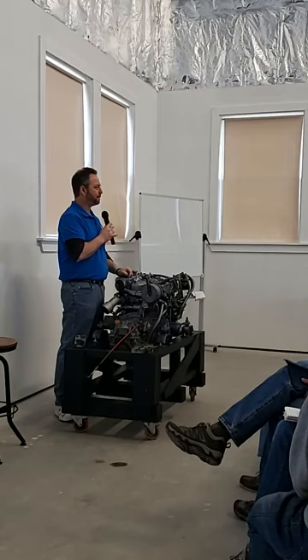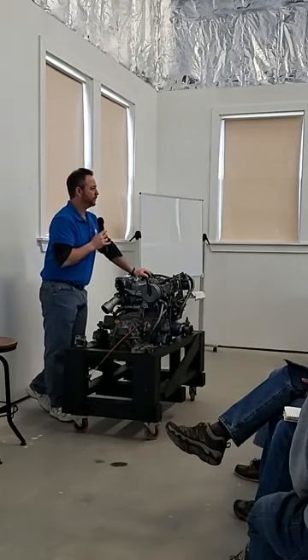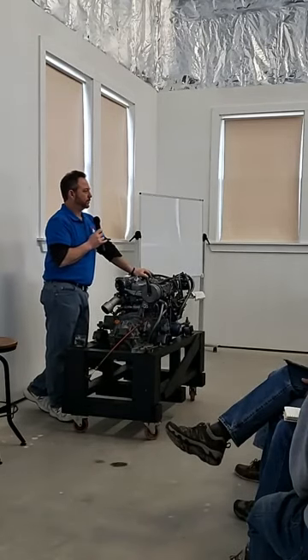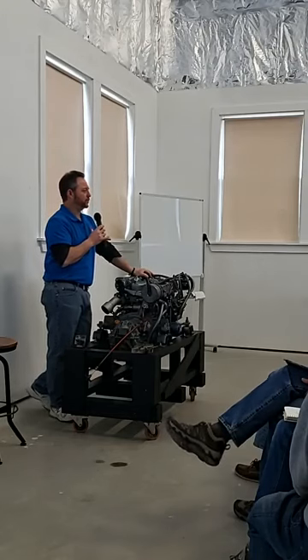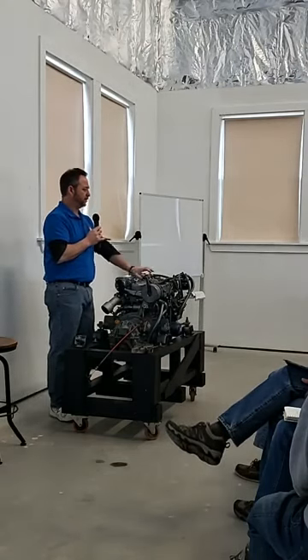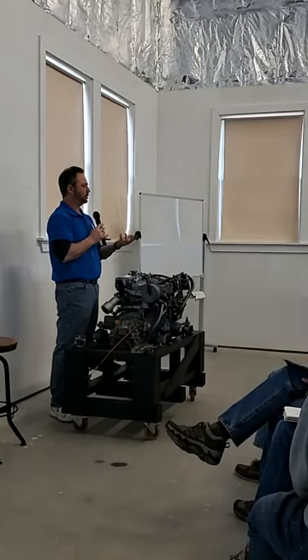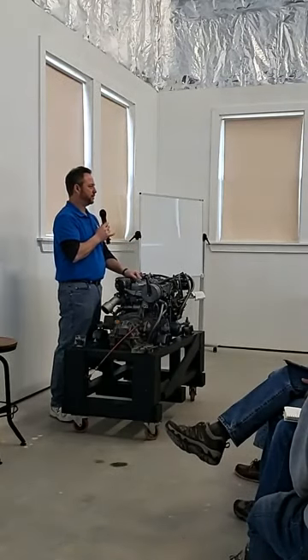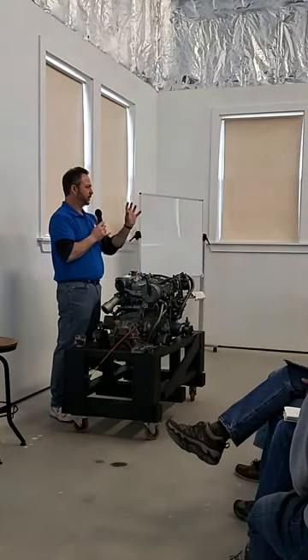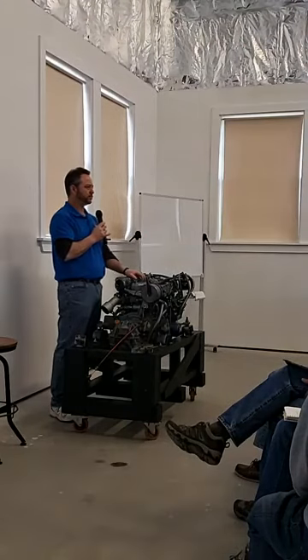I honestly don't use it, use so little fuel inside, I have no idea what the actual tank is. Okay, yeah, and I like when I change the fuel filters for my customers, I like to really inspect the primary filter. It gives me an idea what's going on in the tank, because all the large debris will be captured in that primary.